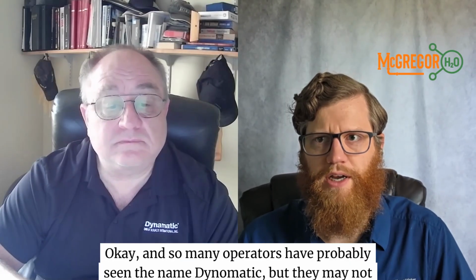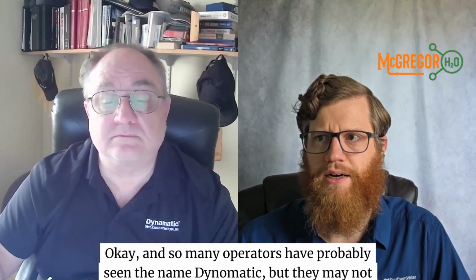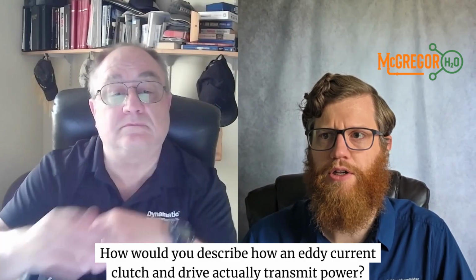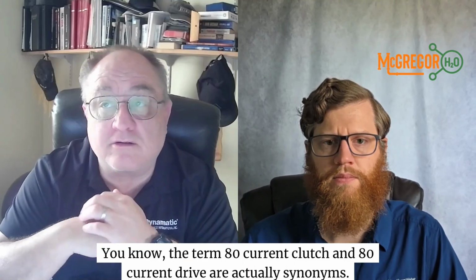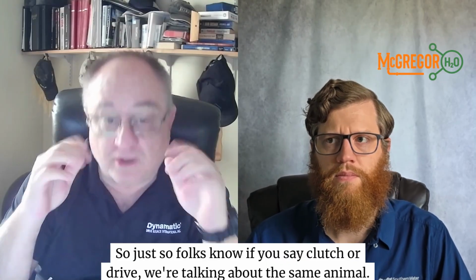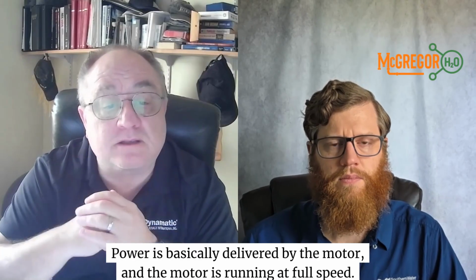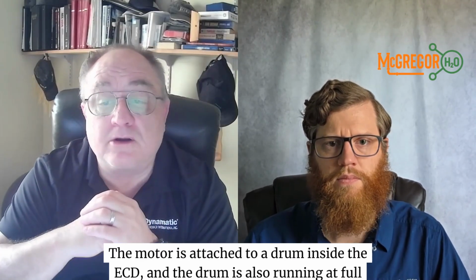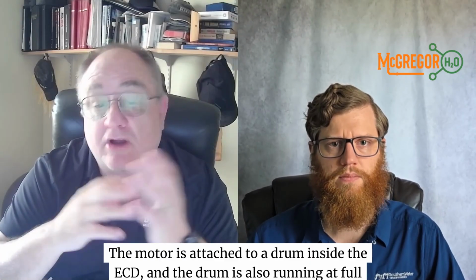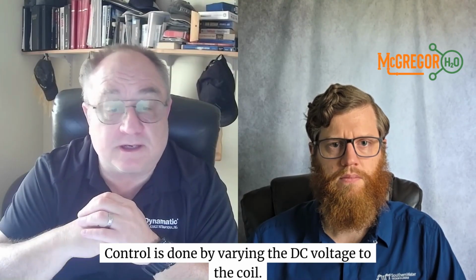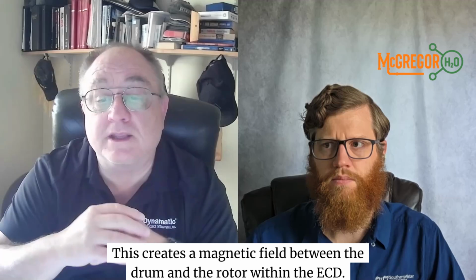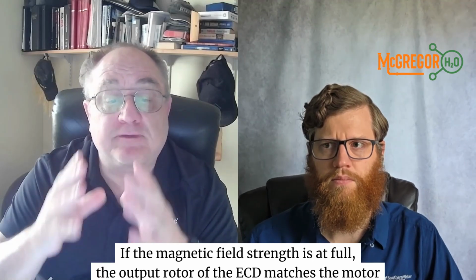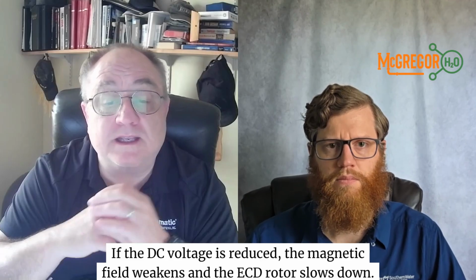Okay. And so many operators have probably seen the name Dynamatic, but they may not know the physics. How would you describe how an eddy current clutch and drive actually transmit power? Fantastic. Good question. The terms eddy current clutch and eddy current drive are actually synonyms. So just so folks know, if you say clutch or drive, we're talking about the same animal. The power is basically delivered by the motor, and the motor's running at full speed. The motor is attached to a drum inside the ECD, and the drum is also running at full motor speed. Control is done by varying a DC voltage to the coil on the ECD rotor. This creates a magnetic field between the drum and the rotor within the ECD. If the magnetic field strength is at full, the output rotor of the ECD matches the motor speed. If the DC voltage is reduced, the magnetic field weakens and the ECD rotor slows down.